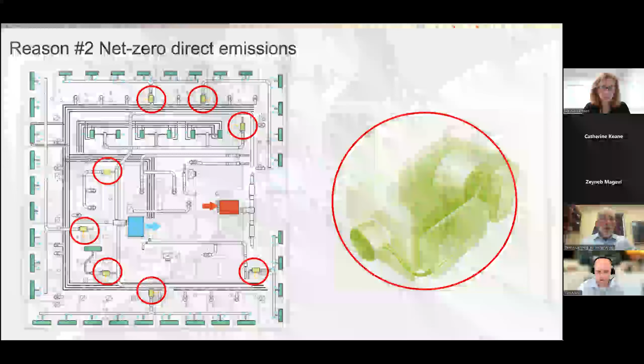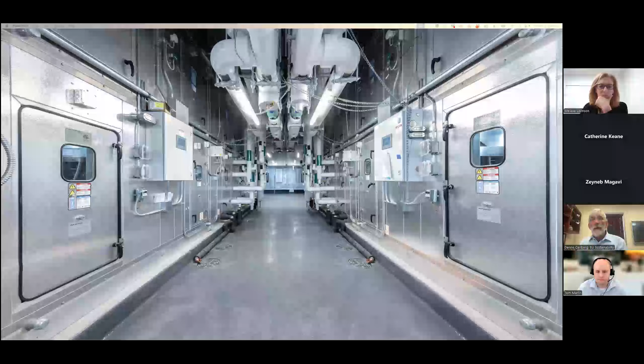To create that healthy indoor environment, buildings require substantial amounts of fresh air from the outside to replace the stale air that's within the buildings. These air handlers are an important part of the energy recovery system of the building. These energy recovery devices have heat recovery wheels, which transfer outgoing thermal energy to the incoming air without mixing the actual air. These dedicated outdoor air systems also dehumidify the incoming outside air, thus making the distributed air more comfortable and removing water from that air, which would otherwise potentially condense on the chilled beams.